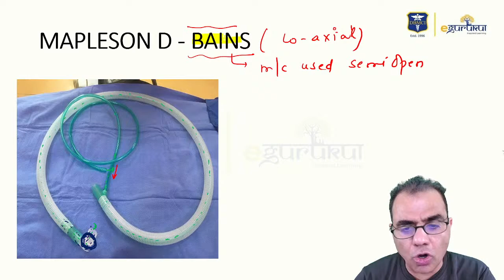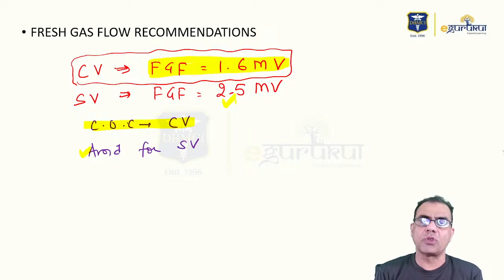B and C we already discussed on this page. B and C stand obsolete. They are no more used. A modification of D, Bain's, is the most commonly used semi-open circuit, and it is the circuit of choice for controlled ventilation, where the fresh gas flow required is 1.6 times the minute volume. Similarly, it should be avoided for spontaneous ventilation because the fresh gas flow requirement is higher, that is 2.5 times the minute volume.